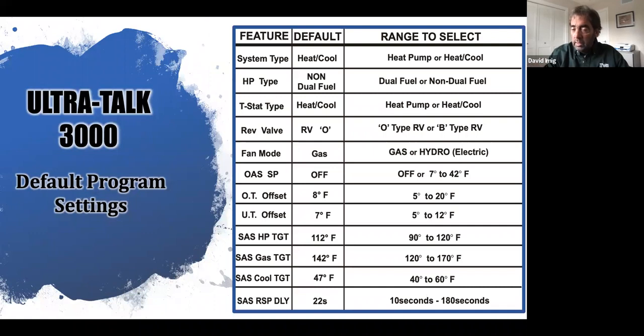In my cooling, I've got a UT offset of 7 degrees. So that means that if I see a temperature down to 40 degrees, I'm going to cycle off that compressor before it ices up, freezes up, and before it slugs back to the compressor. And again, for a period of 3 minutes, and if the cooling call is there and my temperature is safe to operate again, I will bring that cooling call back on. Keep in mind the fan is running during all of this cycling, so it's not a nuisance fan off, fan on operation. It's just the equipment itself, combustion and or compressor, that are cycling.